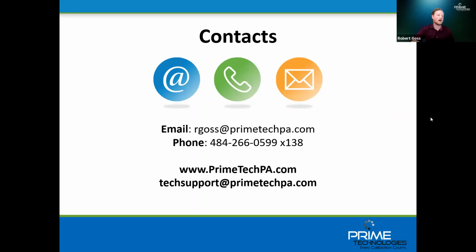Another anonymous one here. If I wanted to have a hybrid system, can I print out a worksheet? Yeah, of course. There are tons of different ways to do this, and this is most likely going to be applicable to any CMS, so I can stay at that level. There are multiple ways, where obviously you can go right into the application. You have your as found, your as left areas of reporting information, and you can just type in your results that way.